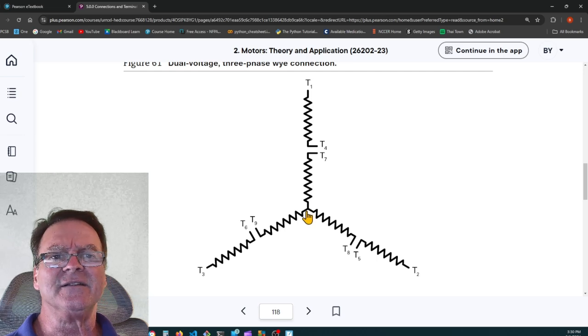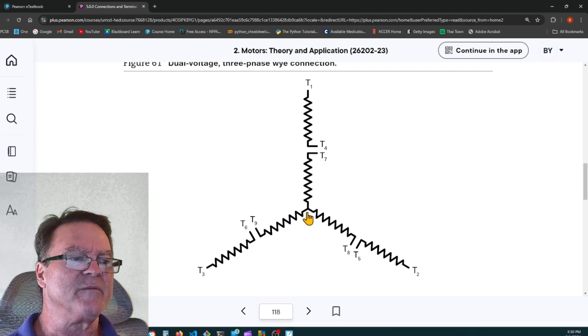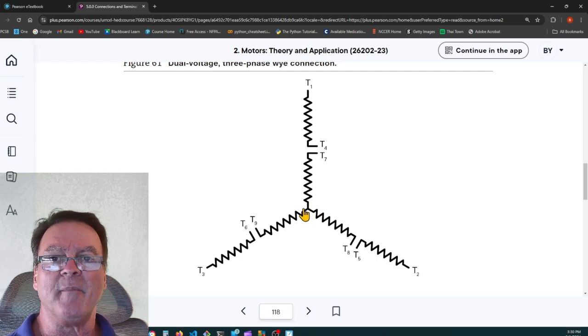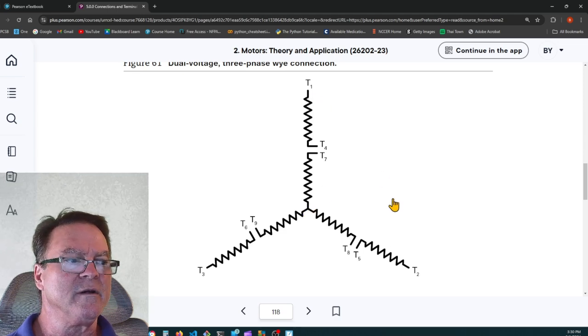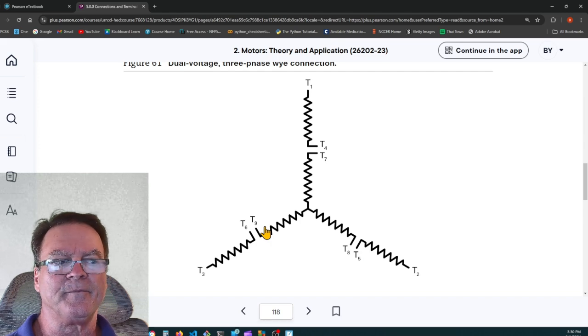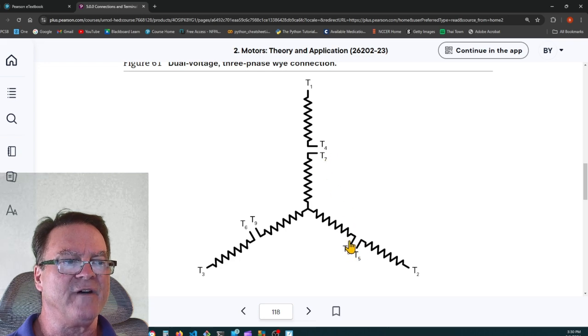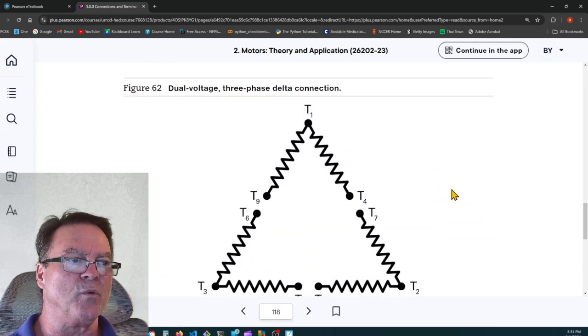It only has 9 leads in the junction box on the side of the motor because 3 of them have been put together and buried. They took 10, 11, and 12 and tied them together in a star pattern, and they buried them. So the leads we see are 1, 2, 3, 4, 5, 6, 7, 8, and 9. We can hook these up in series just by hooking up 4 to 7, 5 to 8, and 6 to 9 for high voltage, or we can hook them up in parallel for low voltage. I'll show you on the magic board.